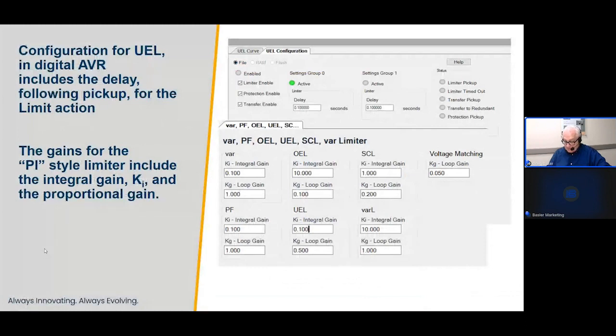The digital excitation controller is provided with configuring software tools for entering, editing, and documenting the settings that are loaded into the controller. The delays and gains apply to actions that are initiated by the pickup of the limiter based on running conditions. The values are in a format that allows conversion to corresponding values that are inputs to the modeling and simulation software. The most modern digital excitation controllers feature testing support with step functions and oscillography for commissioning and tuning, including the documentation of these test results.